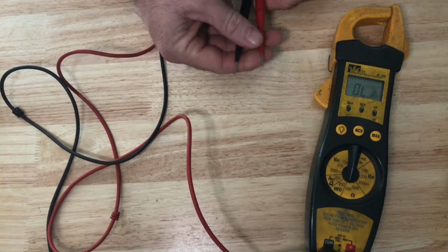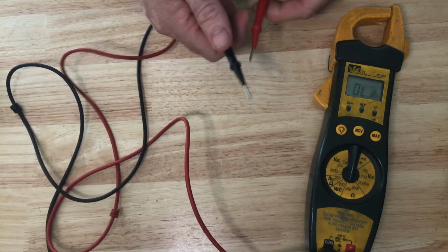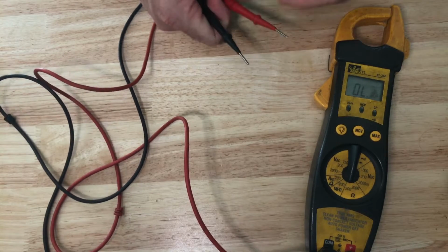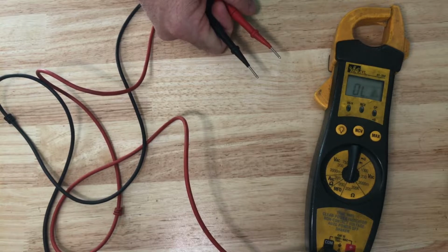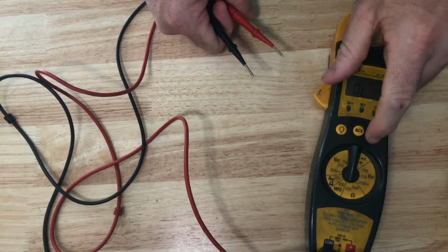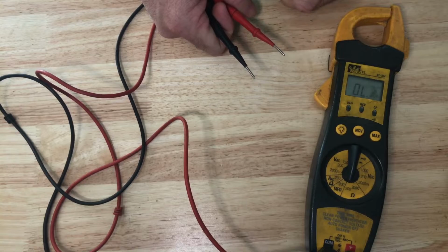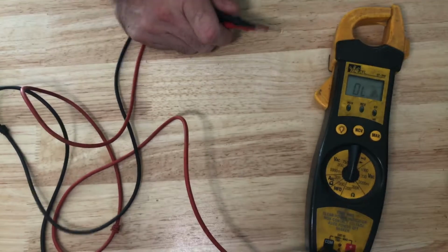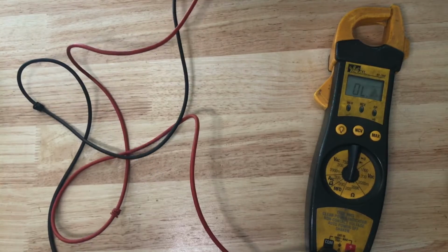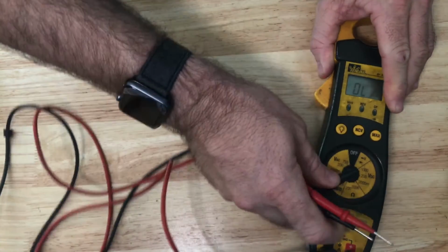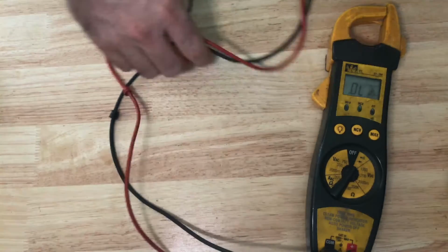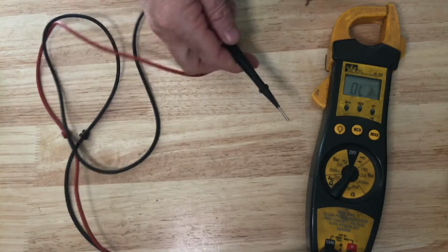Before I do anything, I just want to prove my meter, and I'm going to use a technique we call prove, test, prove. If you want to know more about that, go to the video on voltage testing, where I'll discuss in detail prove, test, prove, and the safety requirements of using that technique when we're doing voltage testing in particular. But for my continuity or resistance testing, my prove here is I just want to know that my meter is working and that it will read a circuit.